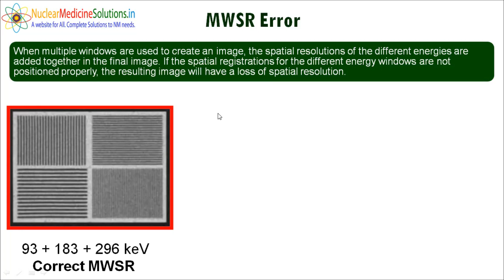When your MWSR is okay, then we are getting a perfect image of a bar phantom. Why? Because the spatial registration for the different energy windows is positioned properly, and because of that the resulting image of the bar phantom is not losing any spatial resolution and is perfectly okay.